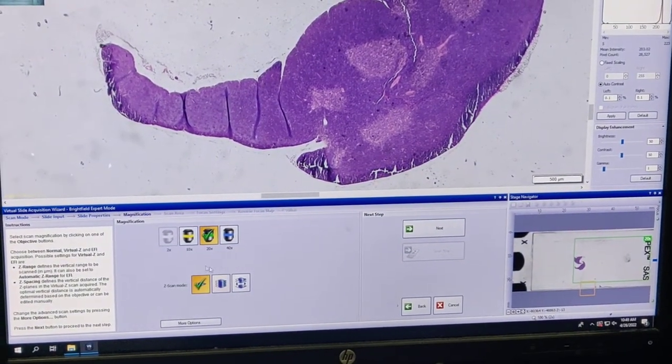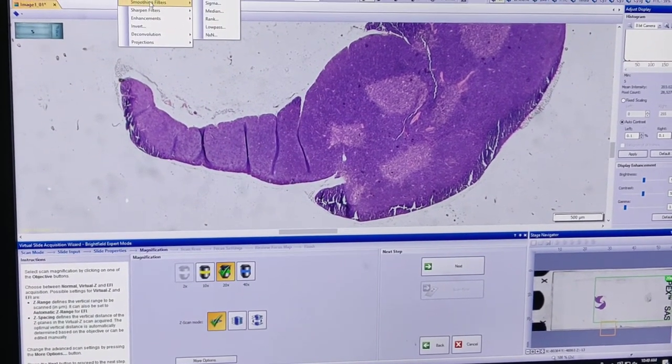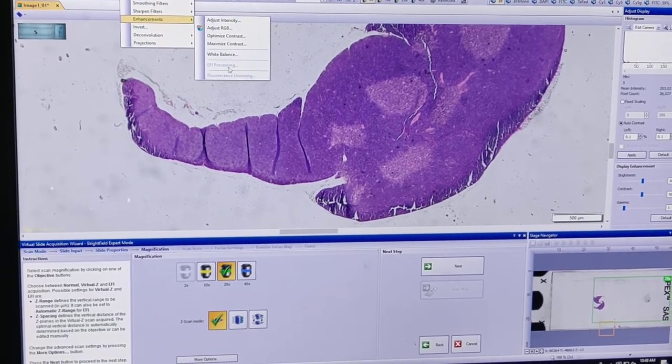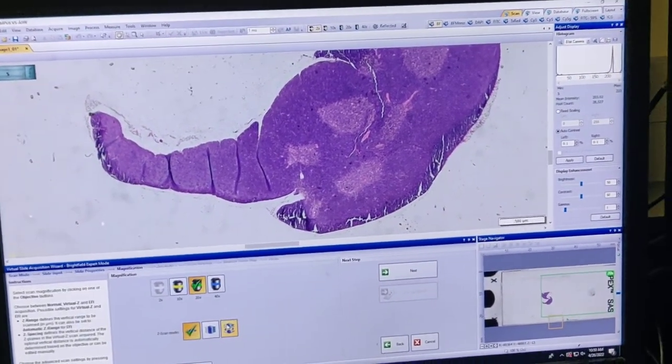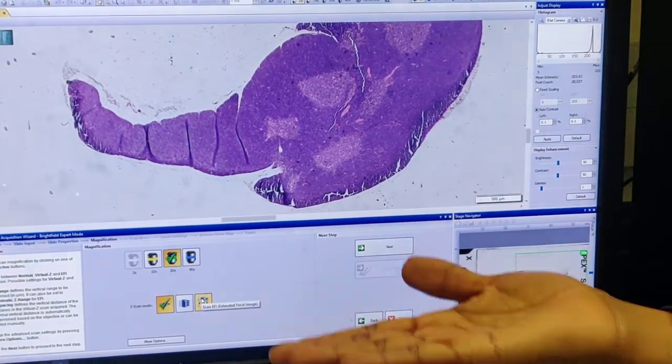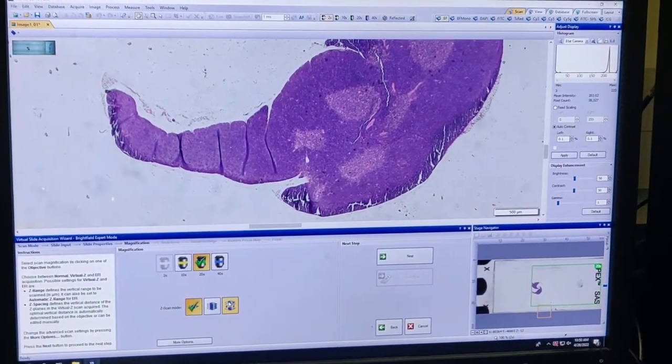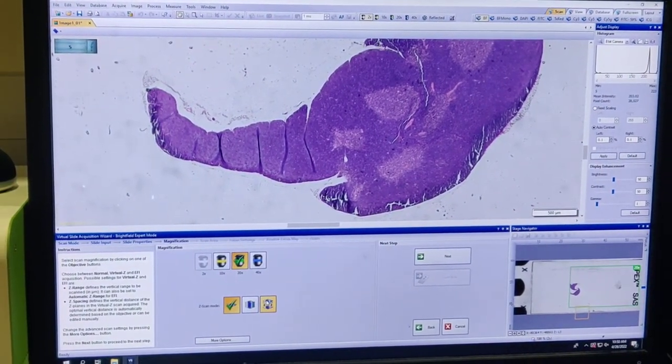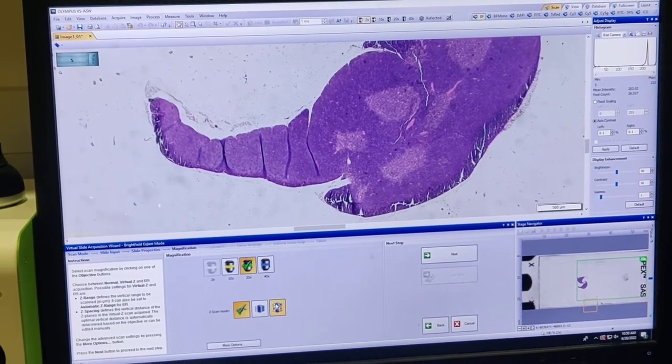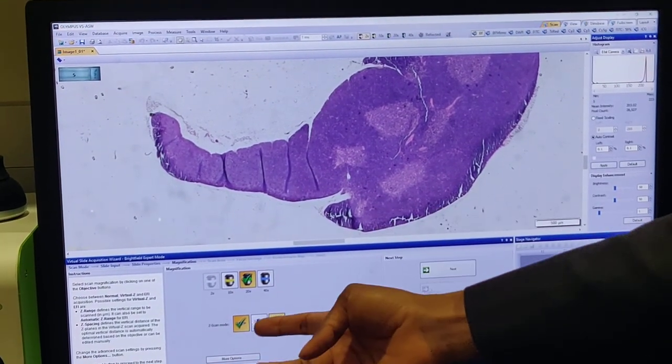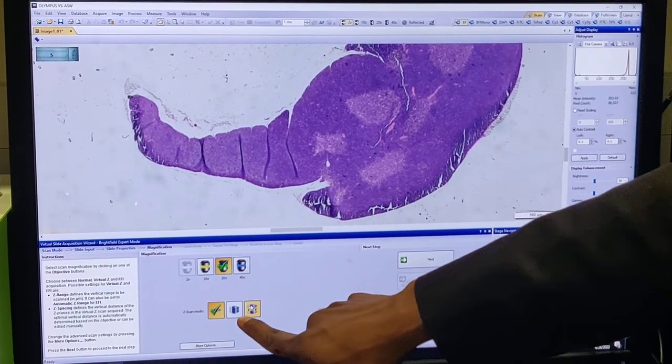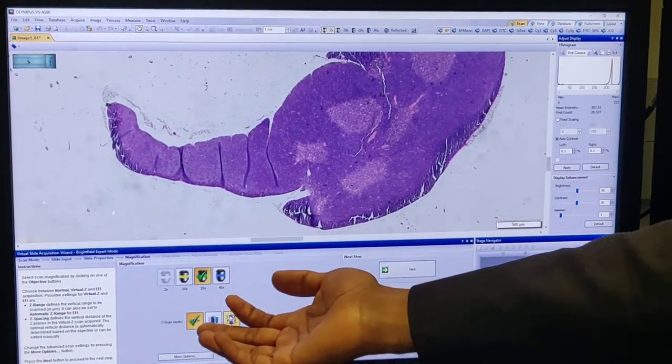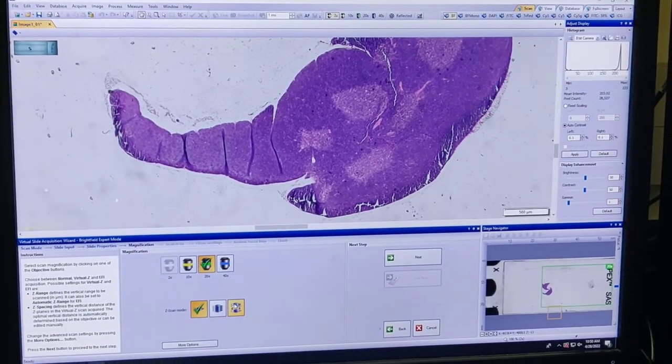In very rare cases when somebody really wants, they can go and take a Z-stack in a small area. There is a protocol here for process and enhancements. There is something called EFI processing, extended focus imaging processing, or you can do it directly using this button. What this will do, it will take all the planes and find the most focused pixel in the entire Z-stack and compress it to one plane. Instead of maximum intensity projection, this is extended focus imaging. So even though they are in different focal planes, all of them can be compressed into one plane. Both of them take longer than usual. If you are having 10 planes, then 10 times more time. So usually one plane is good enough.